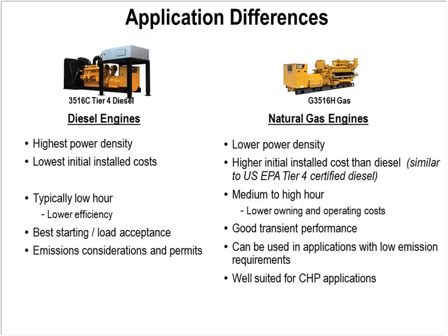We see diesel engines running in typically lower hour applications, and here in the States that's primarily true just because the majority of them are either used for low hour peaking applications or for standby. The gas engines, because of their better fuel efficiency and their ability to have lower owning and operating costs, the owning costs or the maintenance costs, tend to have a lot higher hours of operation. So it's not uncommon for peaking engines on gas to go as high as 4,000 hours a year. And it's not uncommon for gas engines on a worldwide basis to go up to 8,000 hours and run quite well.